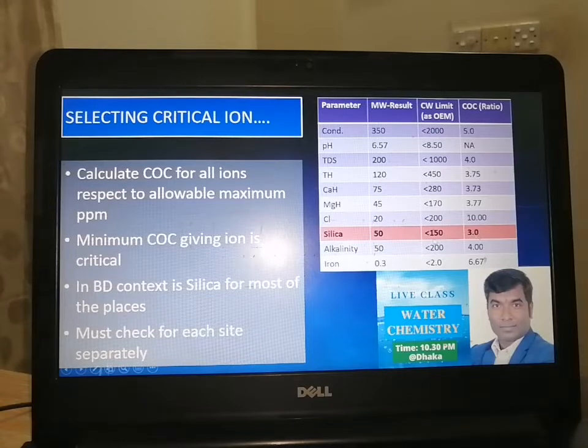For example, if my calcium COC is 4 and silica COC is 3, and I maintain TDS COC 4, then silica will be 200, like 50 into 4, 200. So it crosses the allowable limit and it will create scale. In this sense, here the critical ion is silica. So I think you understand how we can select the critical ion.